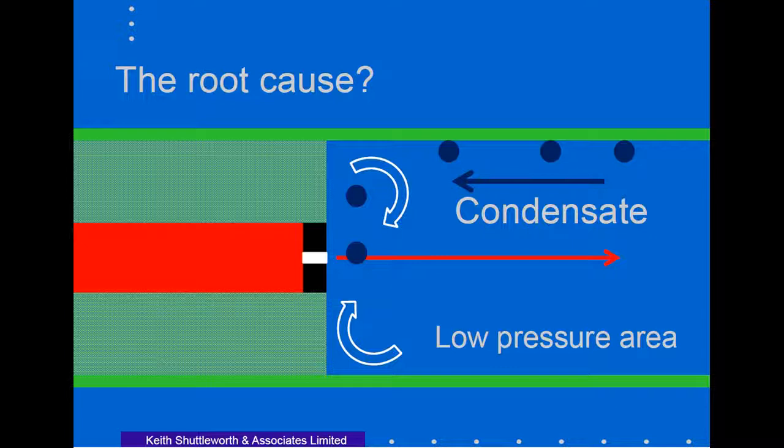It is believed that the flow of steam out of the orifice causes a low pressure area immediately adjacent to the orifice. This causes the condensate to flow in the reverse direction and allows the condensate to be entrained with the steam.